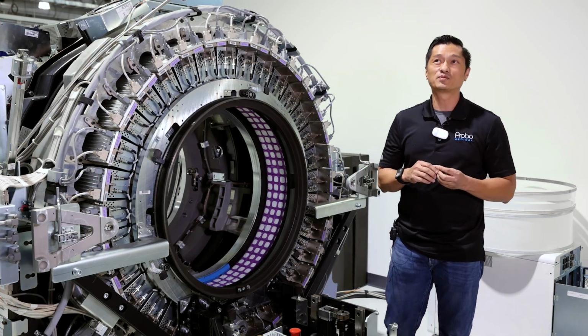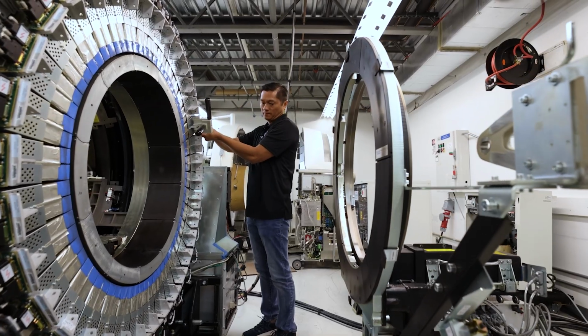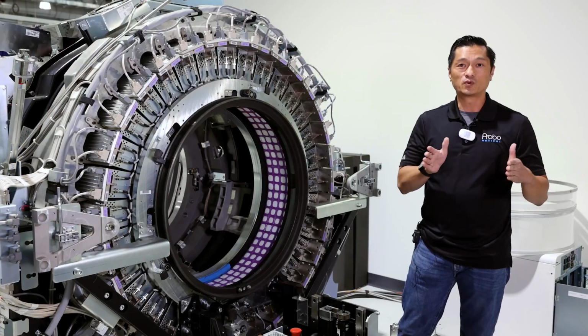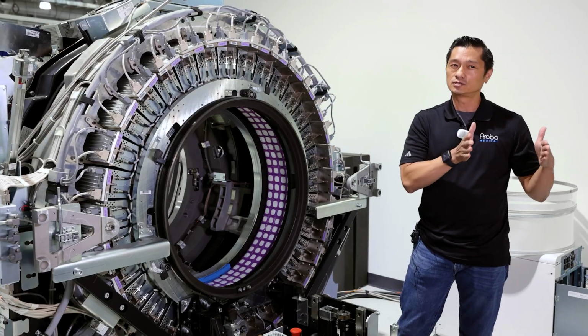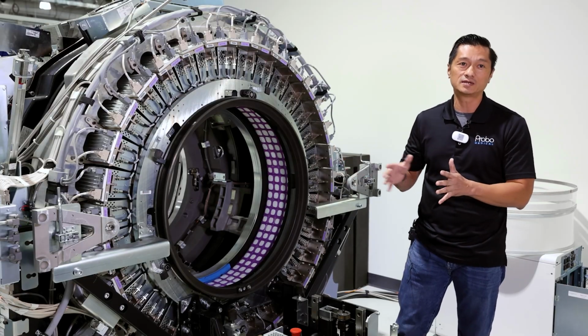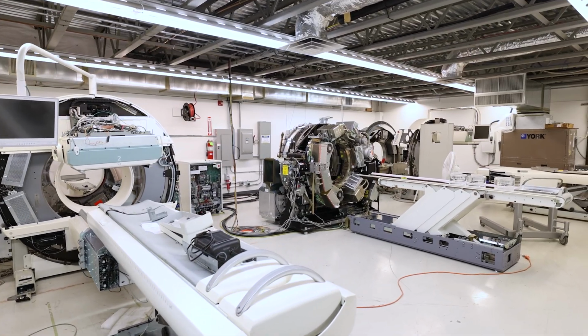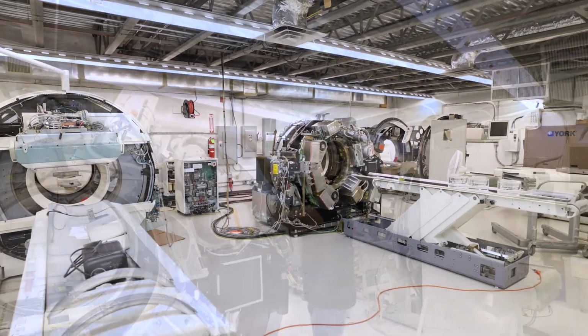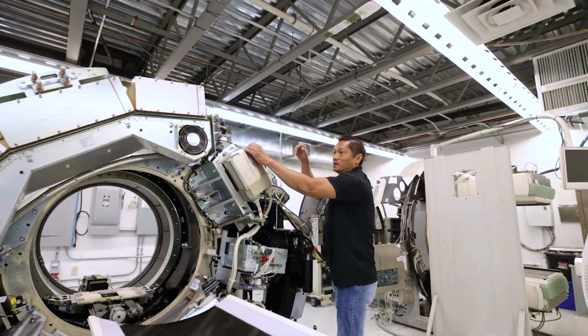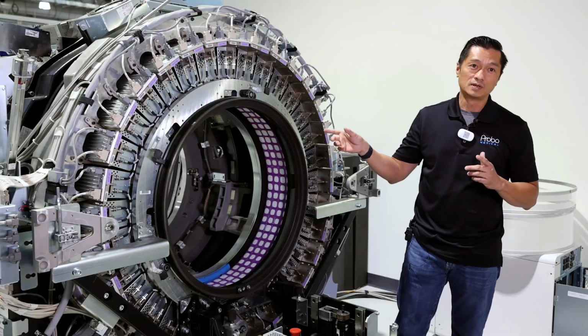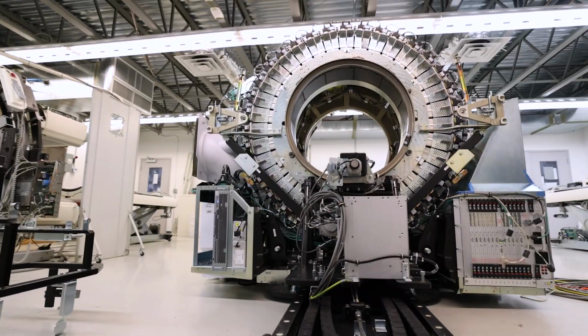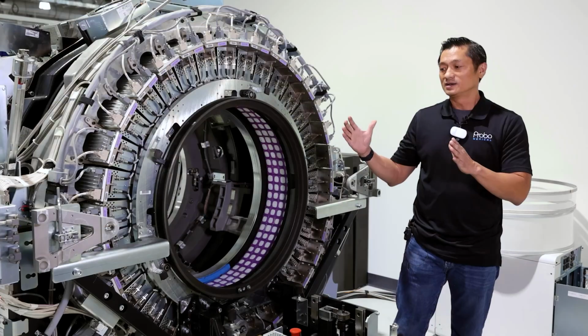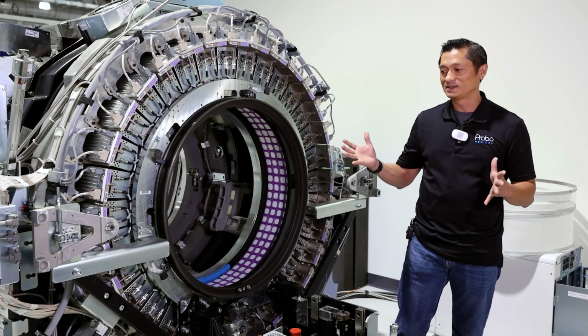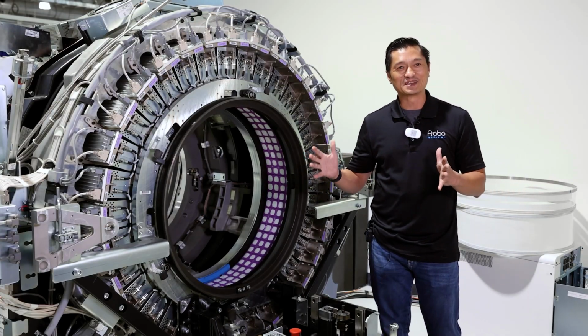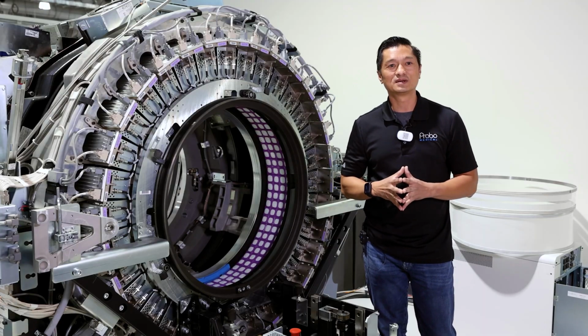Yearly, last year we refurbed close to 10 systems. Normally they take 4 weeks to refurb, but depending on the condition of what we refurb, we can cut it down to 2 to 3 weeks. The PET has more parts than the CT. The CT is really simple, they only have the 1 to 2, but the PETs have more modules, and each module acts like the CT tube scanner. But like I said, they're pretty difficult to refurb.